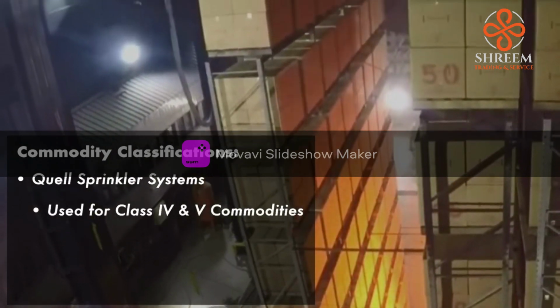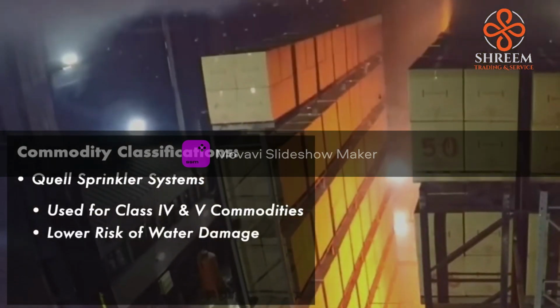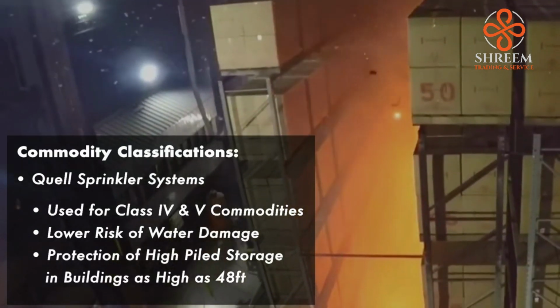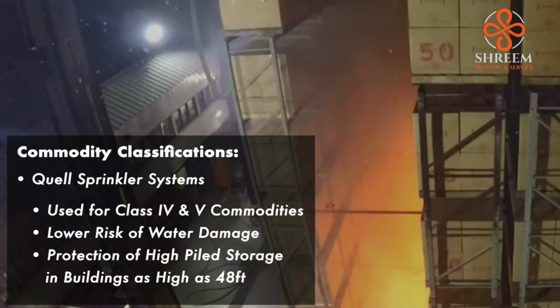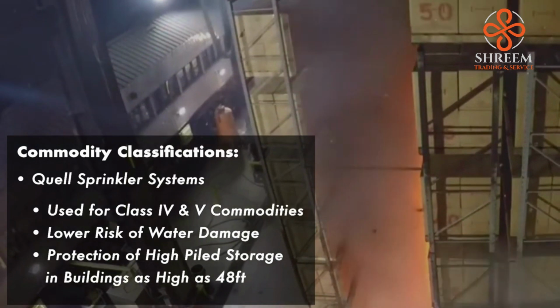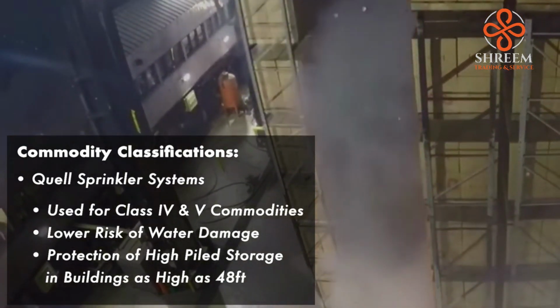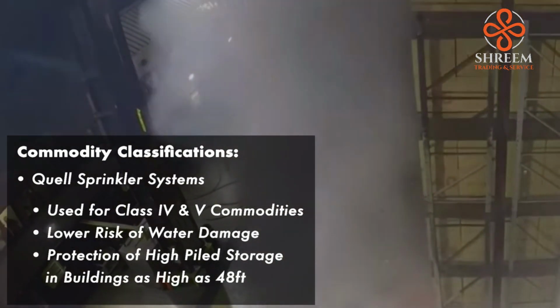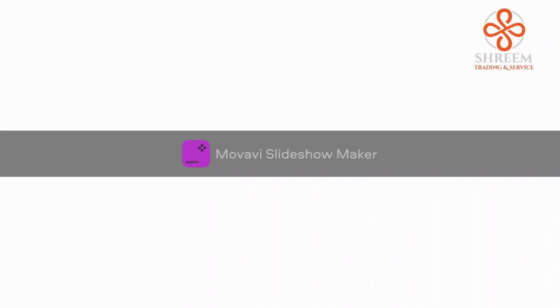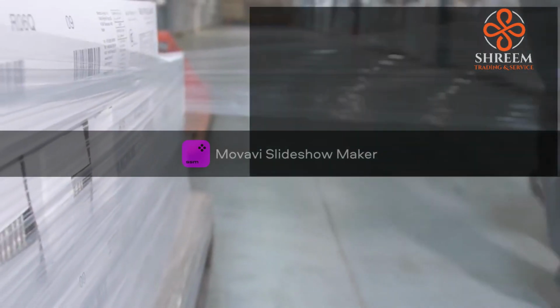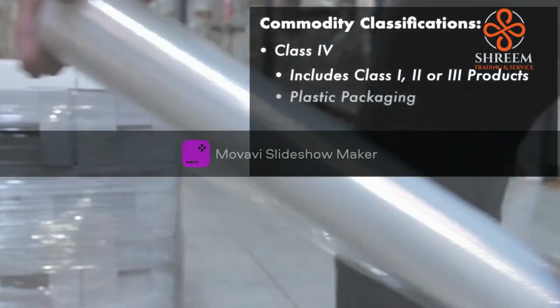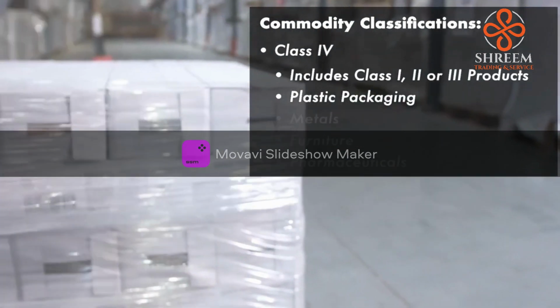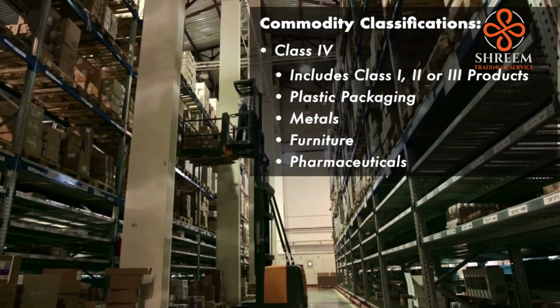For level 4 and 5, you may need quell systems. They're ideal when storing sensitive materials, allowing for a higher level of protection and for protection of commodities piled as high as 48 feet. Consider this if you have Class 4 materials stored in plastic packaging, or items like plastics, furniture, or pharmaceuticals.